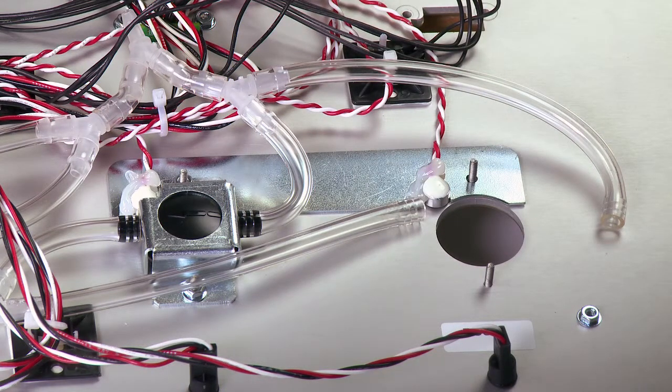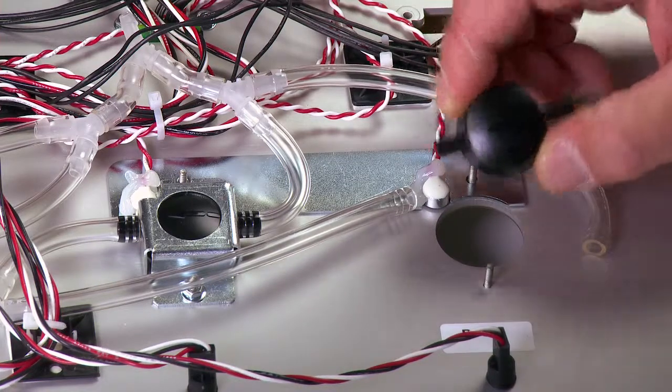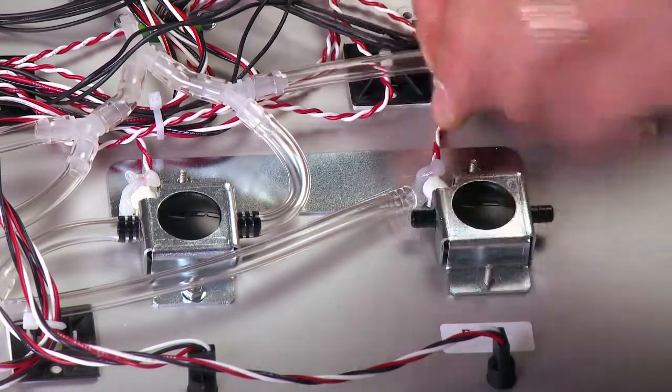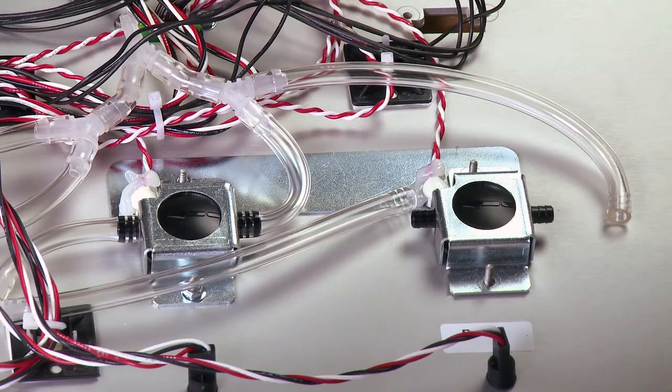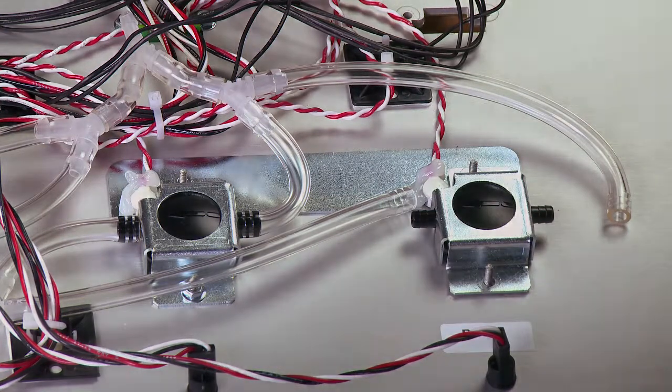You can now remove the bad calibration cup. As you remove it, note the orientation of the arrow on the cup showing the flow of gas from the inlet tube to the outlet tube. The new calibration cup can now be installed. Make sure the gas flow arrow is oriented in the correct direction.